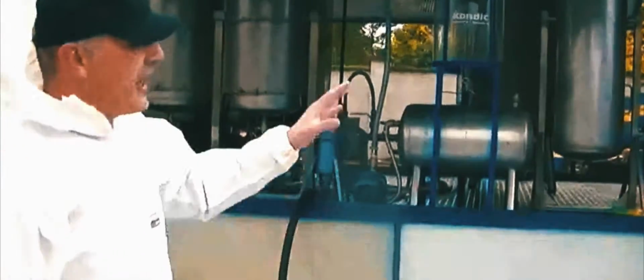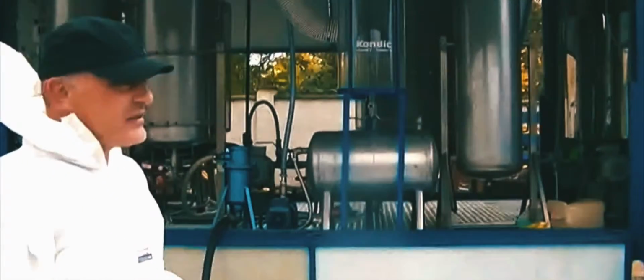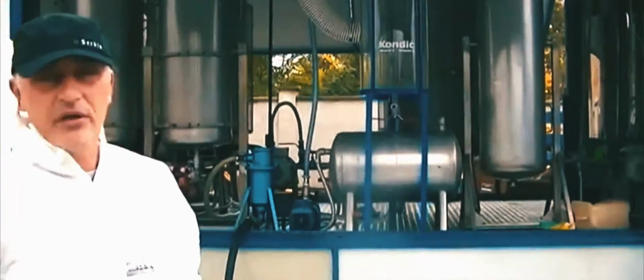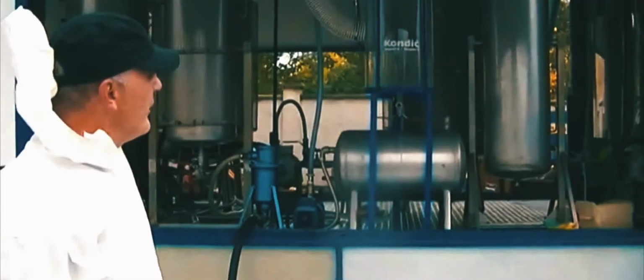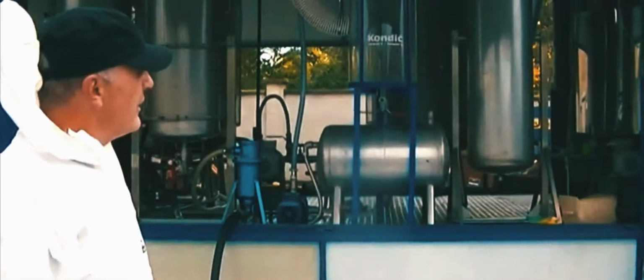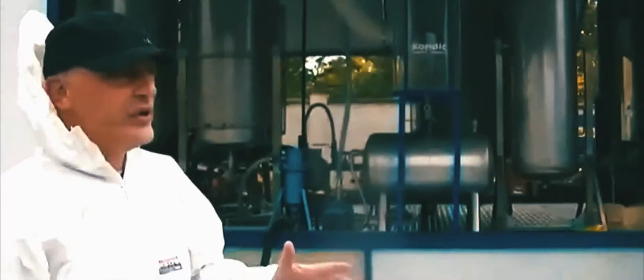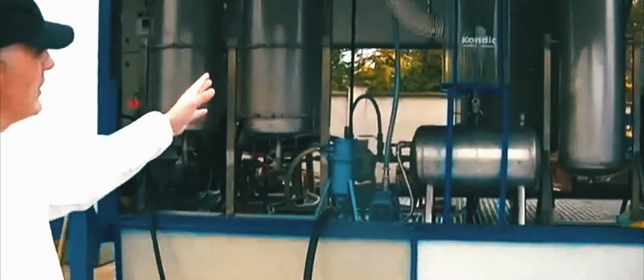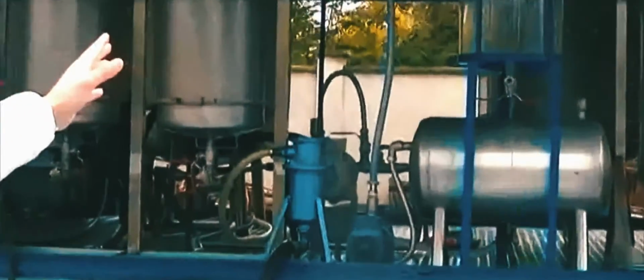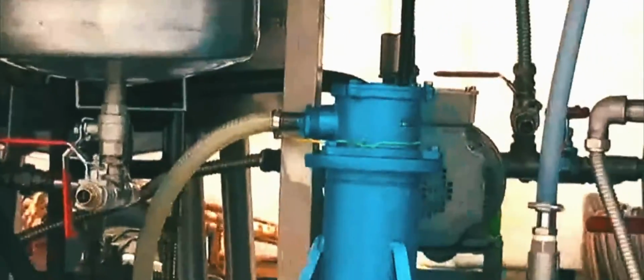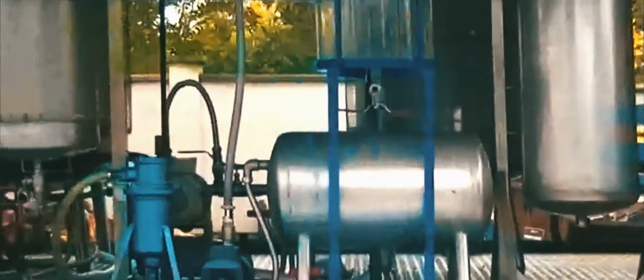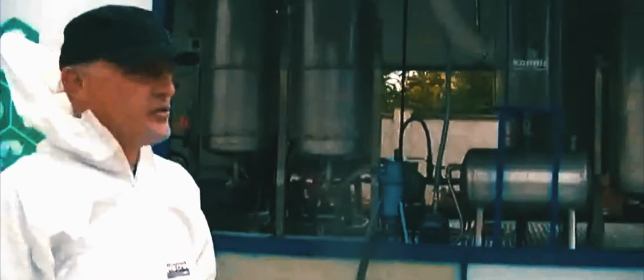After contacting oil with chemicals that remove or destroy PCB, we transport the oil to a different section of the unit where we remove those chemicals from the oil. This is necessary because we want to regenerate the oil so it can be used again - it is not thrown away.